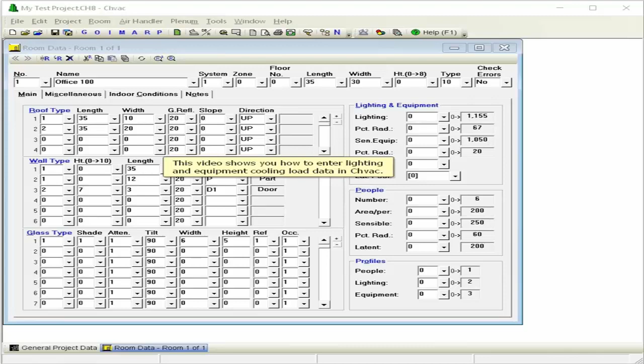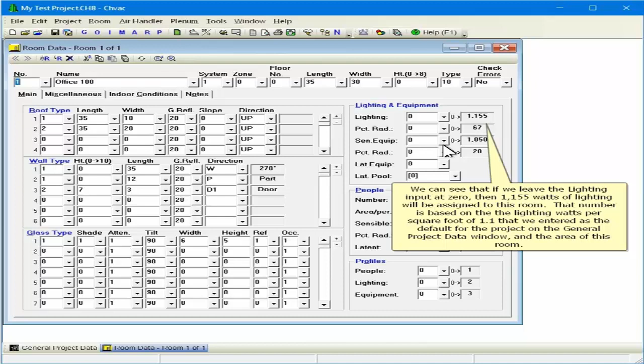This video shows you how to enter lighting and equipment cooling load data in CHVAC. We can see that if we leave the lighting input at 0, then 1155 watts of lighting will be assigned to this room. That number is based on the lighting watts per square foot of 1.1 that we entered as the default for the project on the General Project Data window and the area of this room.